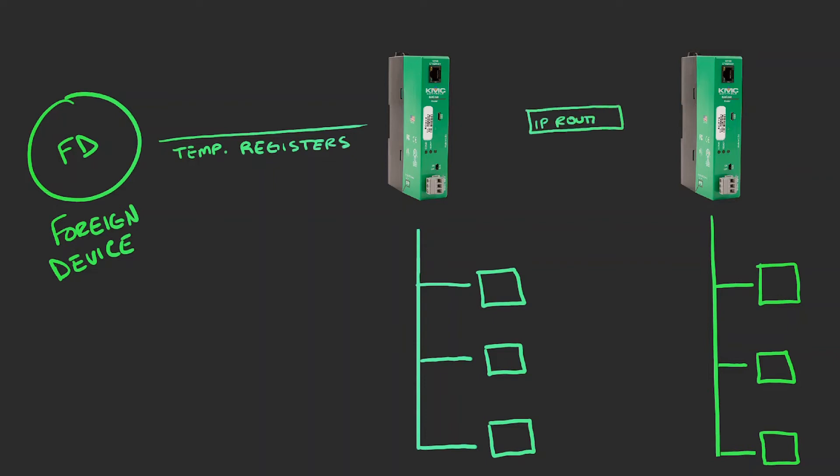By registering with the BBMD, the foreign device becomes a member on the BACnet IP network. It can talk with any BACnet device directly without registration, but will only receive broadcast when successfully registered with the BBMD.